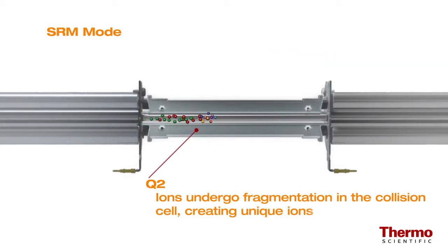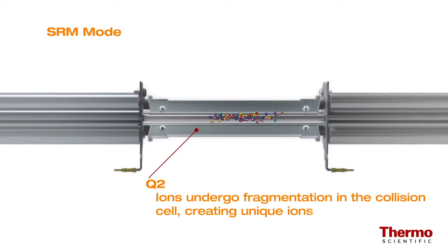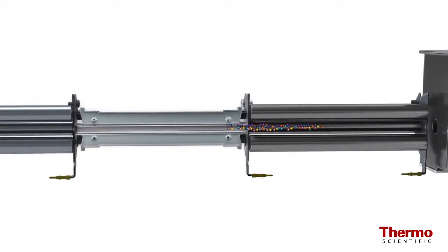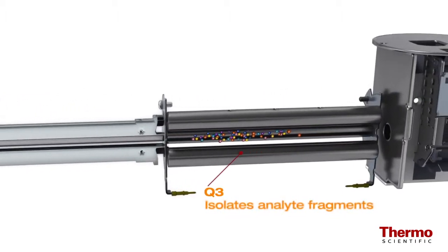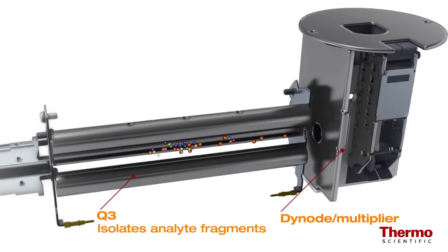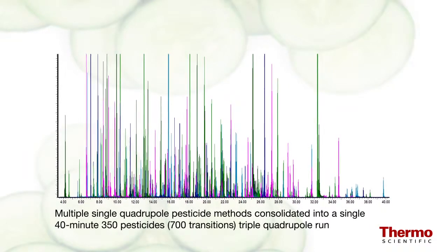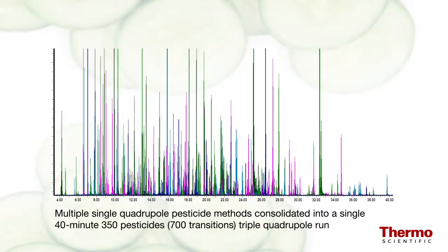With the TSQ8000 triple quadrupole system, these ions can undergo further fragmentation in the collision cell, creating unique ions. The unique ions are then isolated in the third quadrupole, eliminating the potential matrix interference before moving into the dynode/multiplier. This allows you to lower detection limits in complex matrices and enables the operator to combine several methods into one.